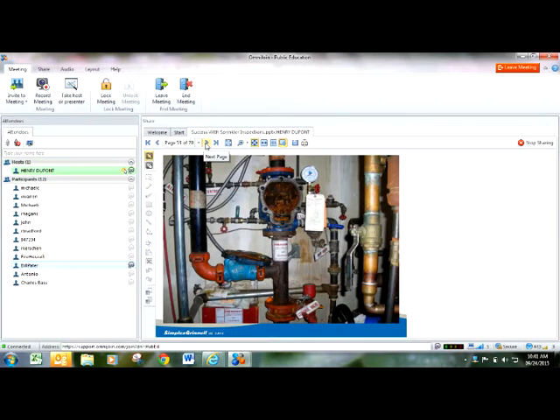If you have a dry pipe sprinkler system, you can still have microbiologically influenced corrosion, and the way to mitigate that, this is new technology, is to flush all the debris out, get it cleaned up, and then install a nitrogen generator air compressor. So you replace the air compressor on the dry pipe sprinkler system with a nitrogen generator, and it's not as expensive as it sounds. The nitrogen generator pushes nitrogen into the sprinkler system instead of oxygen. As the system gets completely freed of oxygen, nothing can grow in that system.